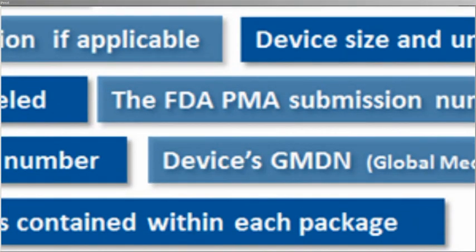There are two additional acronyms I'd like to define here as well. The first is pre-market approval, or PMA. This is the number that the FDA will assign to a Class III medical device after they've approved it for sale. And the GMDN, which is the Global Medical Device Nomenclature Code — a global code that's used to define specific types of medical devices.